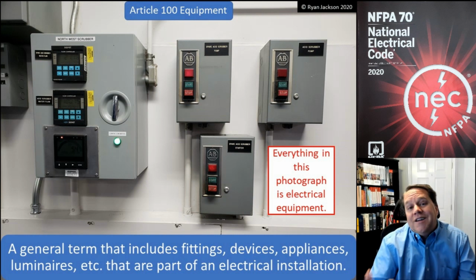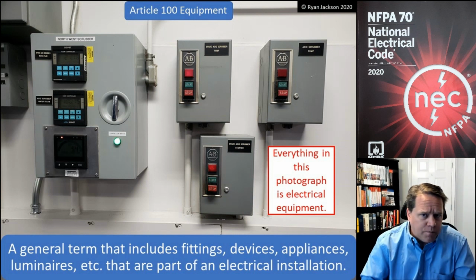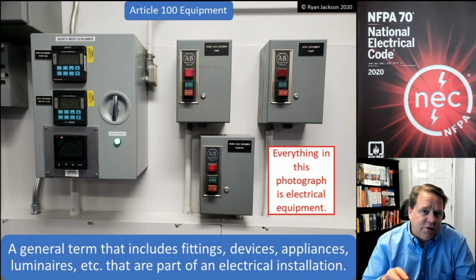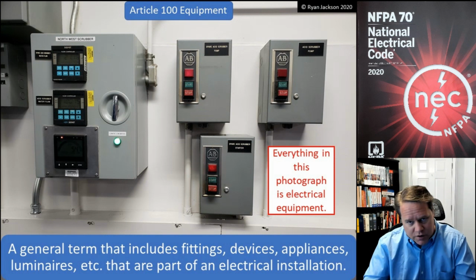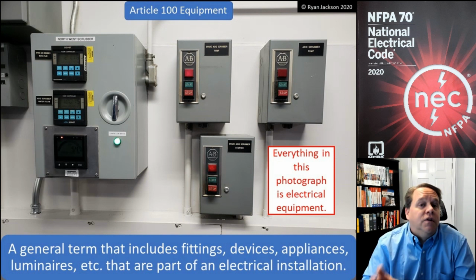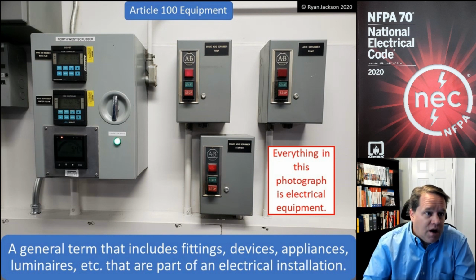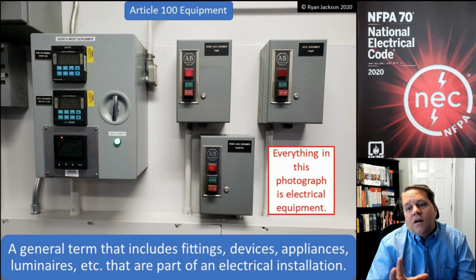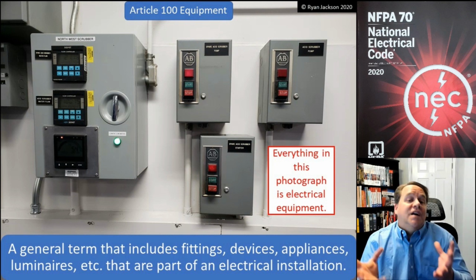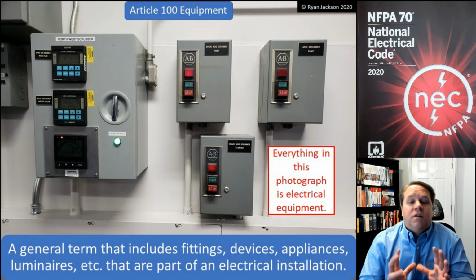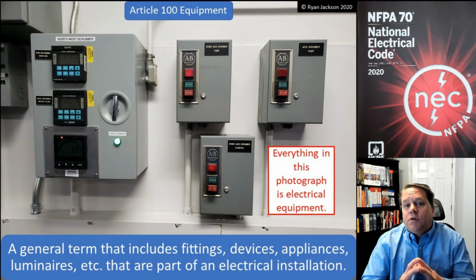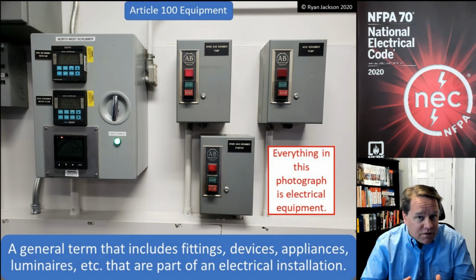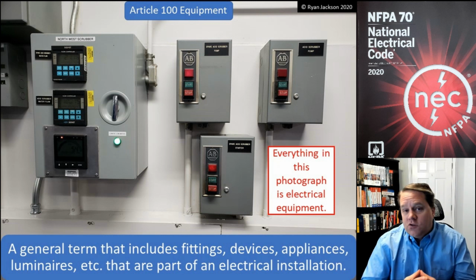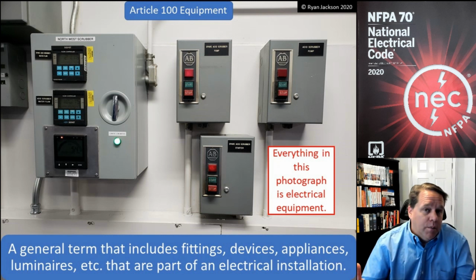In fact, if you go to 90.2(A), the scope of the code, it says this code covers the installation and removal of what? Conductors and equipment. All right, so everything we install is equipment. And it's important that you understand that this definition is intentionally broad, because sometimes we have rules that apply to all equipment. All right, 110.2 says all equipment ultimately must be approved.